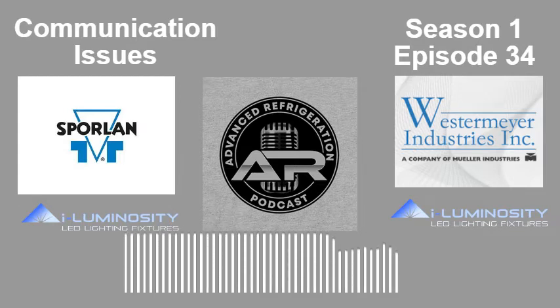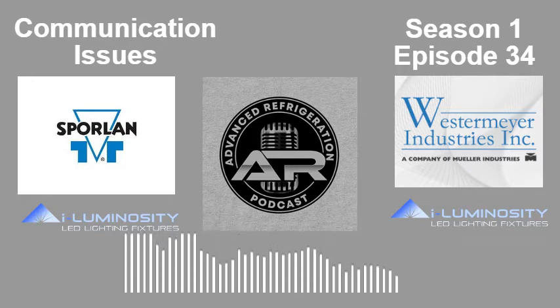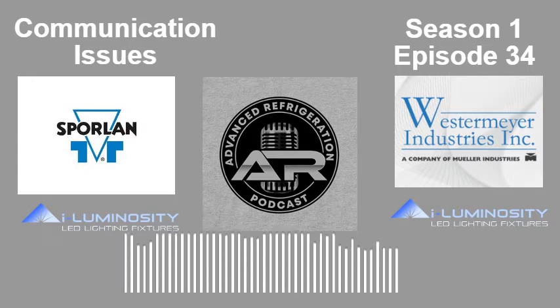No, what I was going to say is on Danfoss they have, like you said, the 485 and the Echelon. Echelon is typically used for, or the TP78 is usually used for all the IO boards, all the inputs and outputs. The 485 that's on the boards, typically there's only one port, and that's usually used to communicate from controller to controller.